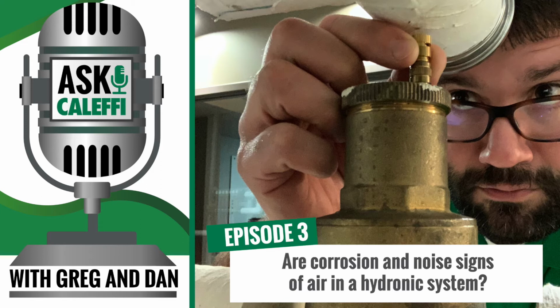Yeah. So when somebody picks out the right product, we have to talk to them about installation. Mm-hmm. Being a pass-through device, does it always have to be on a horizontal pipe, Greg? We have options to install in a vertical pipe, but we only go so far in flow rate with those. Being on a vertical pipe, you're not passing directly through the coalescing mesh in the body. It's kind of like a side discharge. So it will bypass the water off to the side through a coalescing mesh and then back into the vertical pipe. Because of that, the body's a little smaller, the coalescing mesh is a little smaller. It still does a great job of removing air, but they're only good out to about 10 gallons per minute.